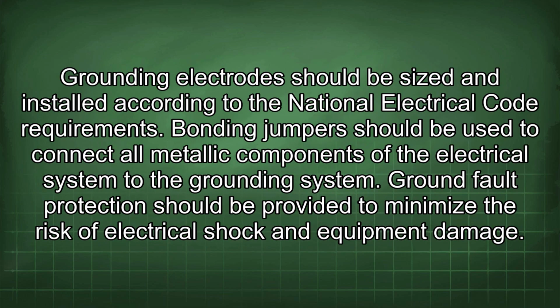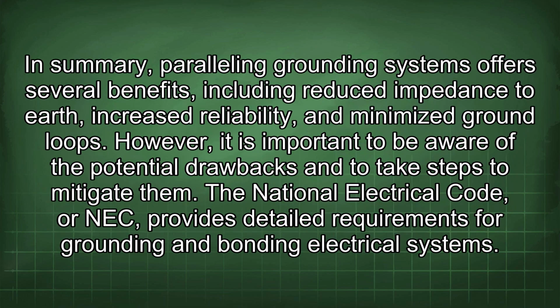Grounding electrodes should be sized and installed according to the National Electrical Code requirements. Bonding jumpers should be used to connect all metallic components of the electrical system to the grounding system. Ground fault protection should be provided to minimize the risk of electrical shock and equipment damage. In summary, paralleling grounding systems offer several benefits, including reduced impedance to Earth, increased reliability, and minimized ground loops. However, it is important to be aware of the potential drawbacks and to take steps to mitigate them.